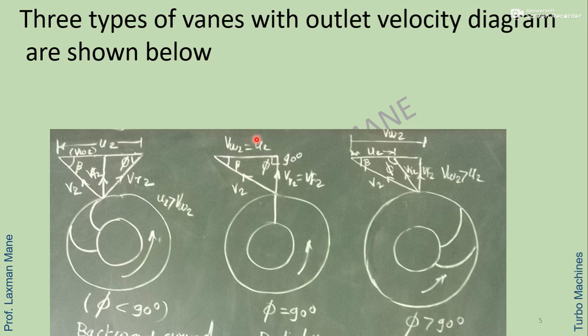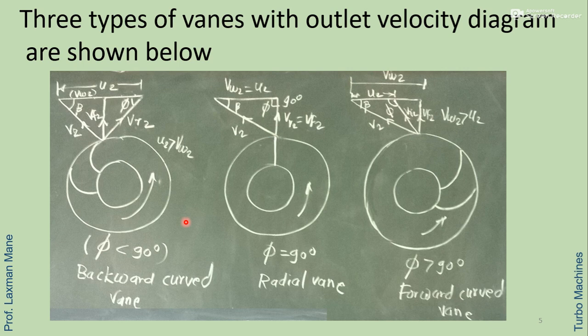These three types of vanes with their outlet velocity diagrams are shown here. For the backward curved vane where phi is less than 90 degrees, the component u2 is greater than vw2. For the radial vane with phi equal to 90 degrees, the whirl component at outlet equals the blade velocity at outlet. For the forward curved vane with phi greater than 90 degrees, vw2 is greater than u2.